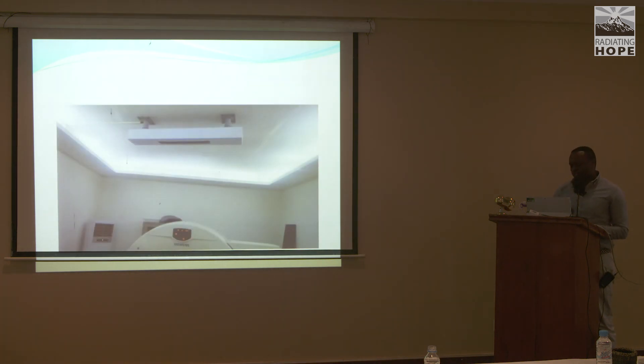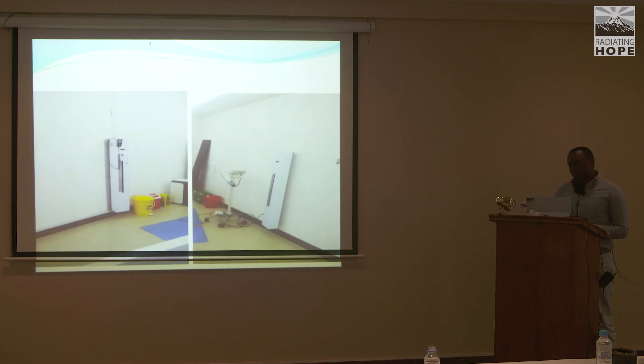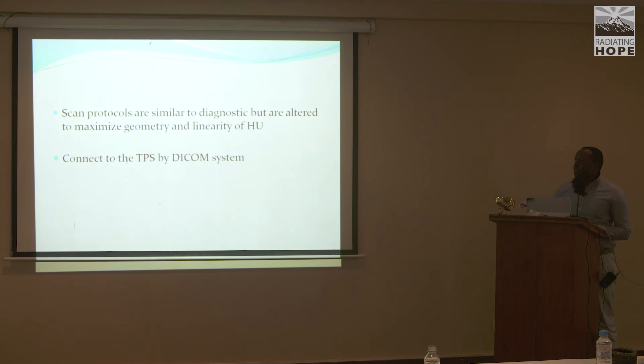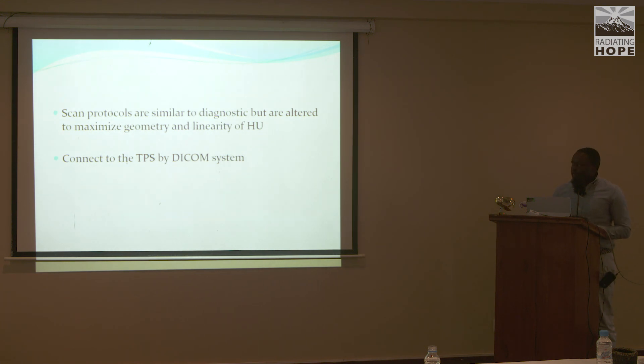You also need external lasers — this is the sagittal, and these are the left and right. Then we continue with the scanning. Normally the scan protocol is almost similar to the diagnostic one, but there are some alterations in the settings for maximisation of geometry and linearity on the Hounsfield unit. The simulator is connected to the TPS by DICOM system, and then we continue with the contouring and planning.